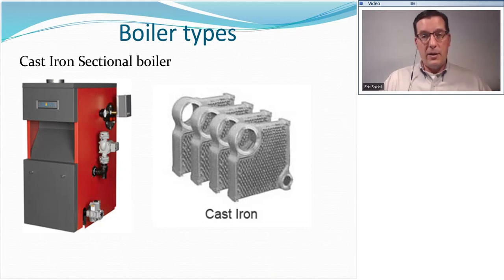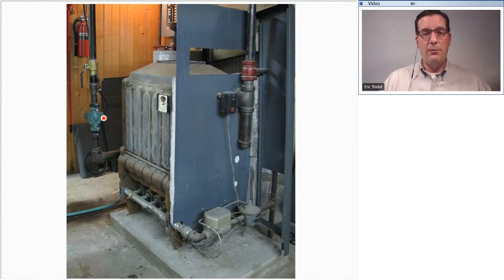Those flames and products of combustion would go right up in between the sections and come out the top. At the top, there's a big metal box literally bolted down and sealed with a special sealer called pyroseal or furnace cement. And this is where all those flue gases would accumulate to connect to the common flue, which would attach to the top of this. One thing I want you to pay attention to on this old cast iron boiler is very likely there's nothing wrong with it. It's probably not leaking water, at least.